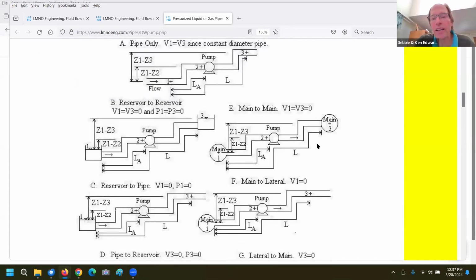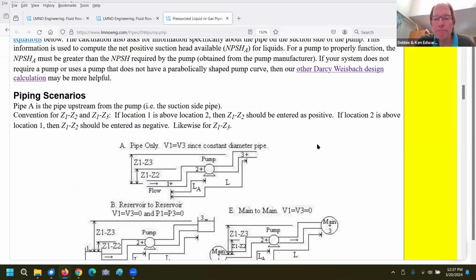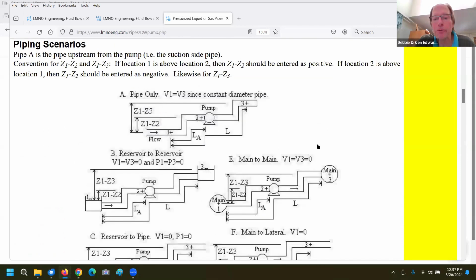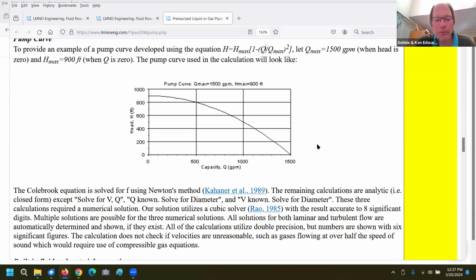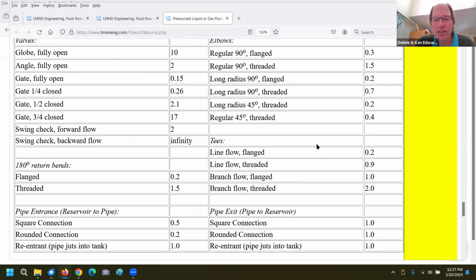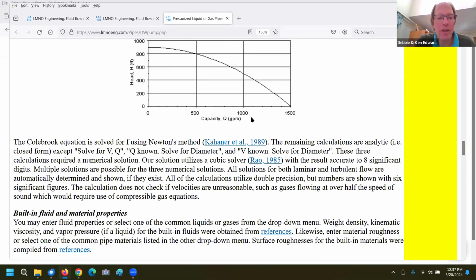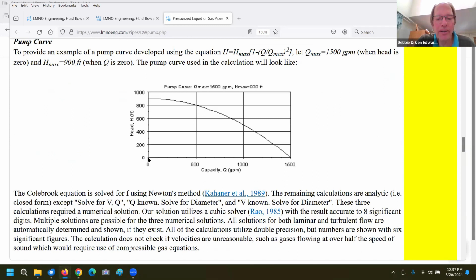And then it'll intersect it with what we call the system curve, which is analyzing the system at different flow rates. So you get a curve. Do I have a system curve on here? I guess I don't. System curve goes in the opposite direction. So a system curve would start at, say, 0 head and 0 flow. When you have 0 flow, there's no head required. But then your system curve would kind of go in this direction. And so the intersection of the system curve and the pump curve gives you your operating point. So that's the actual flow rate and head that will go through that system with this pump.